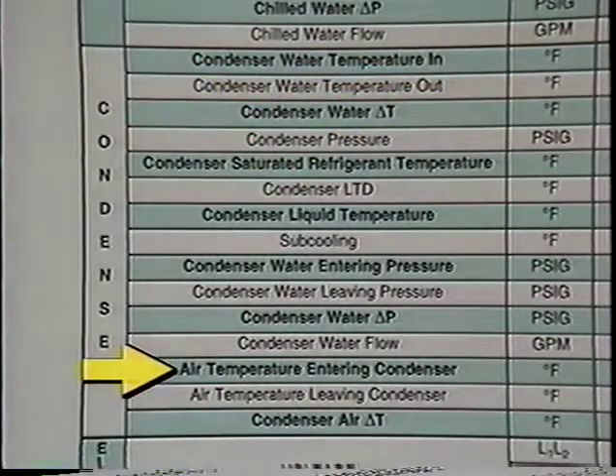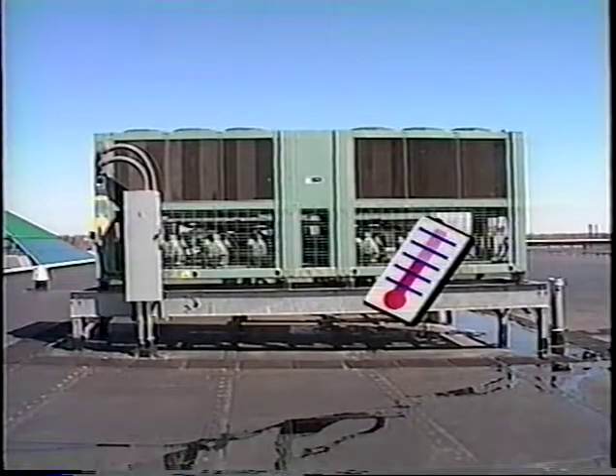Air temperature entering condenser. Measure and record the outdoor ambient air temperature entering the condenser. This is a very important factor on air-cooled condensers because it provides a reference to what the condenser saturated refrigerant temperature operating conditions should be.